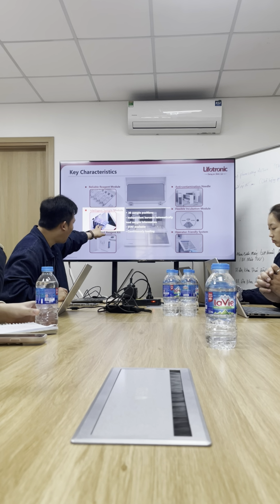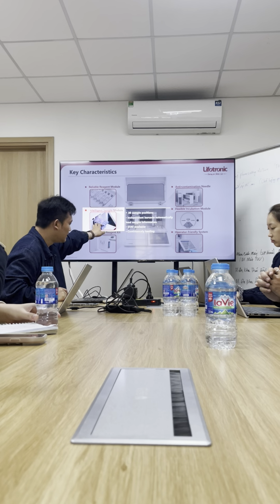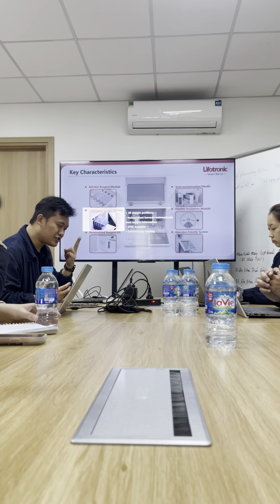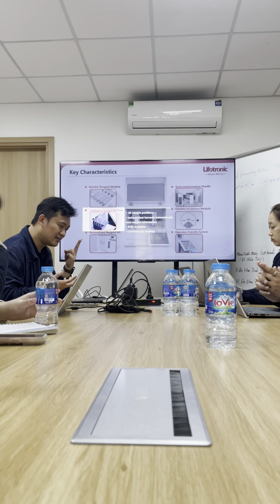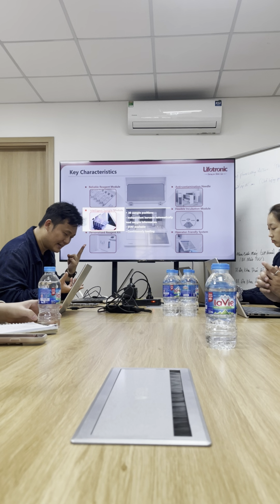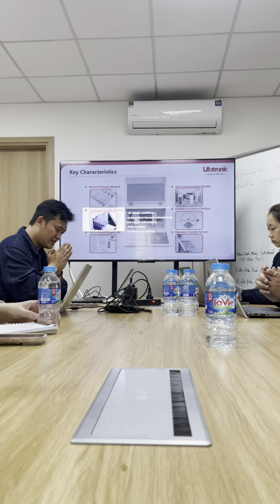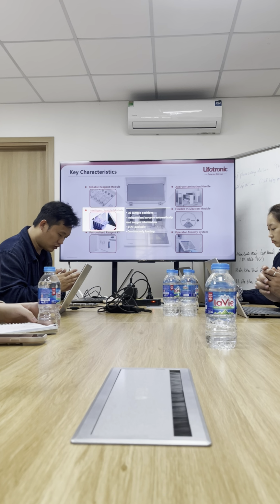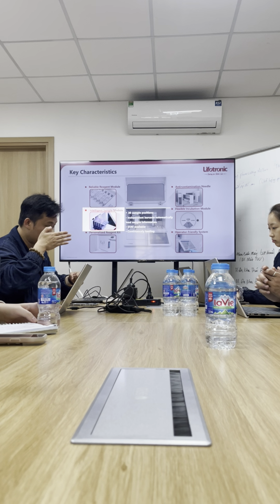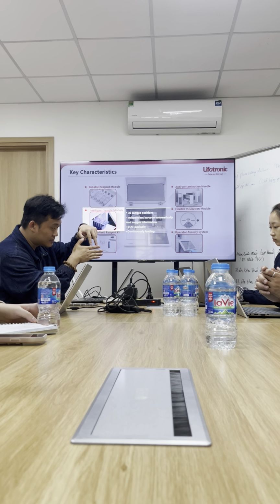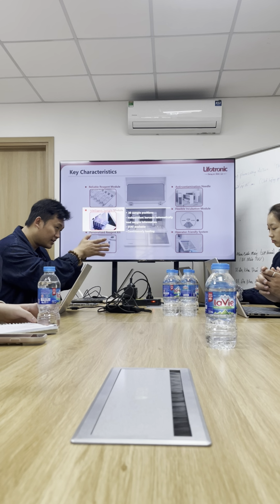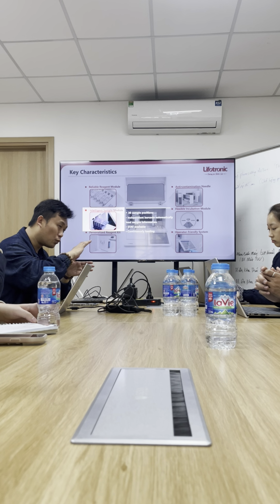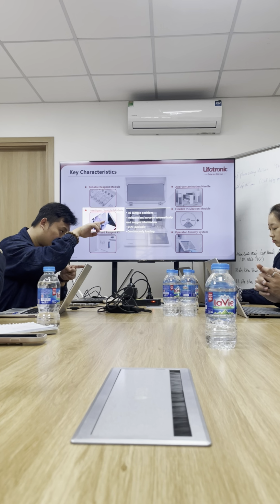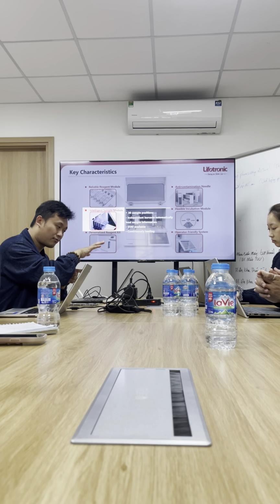For example, now you load two sample racks, and now an emergency sample comes in for cardiac testing for troponin I. This sample is an emergency sample, it cannot wait. So you can load it in the third rack, setting these samples as stat, even while the other two racks are routine operation. You can set a stat. The stat emergency sample will start with the first priority.